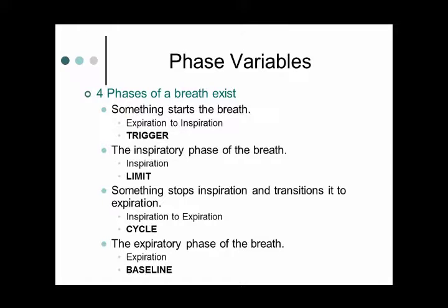Something's starting the breath, something's going on during the breath, something's ending the breath, and then finally something's happening between breaths. That seems like a lot of BS, doesn't it? No, it makes a difference though, because we're going to talk about how a pressure support breath ends differently than a pressure control breath.